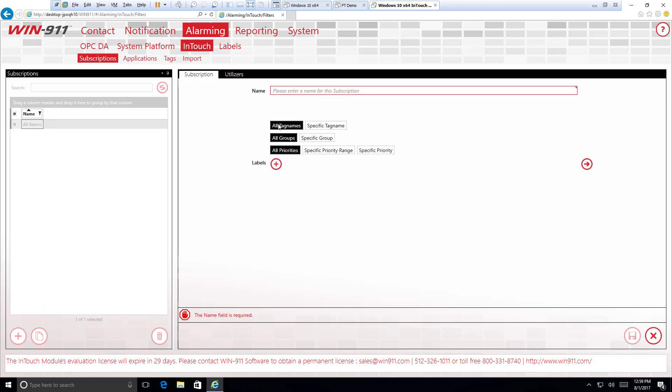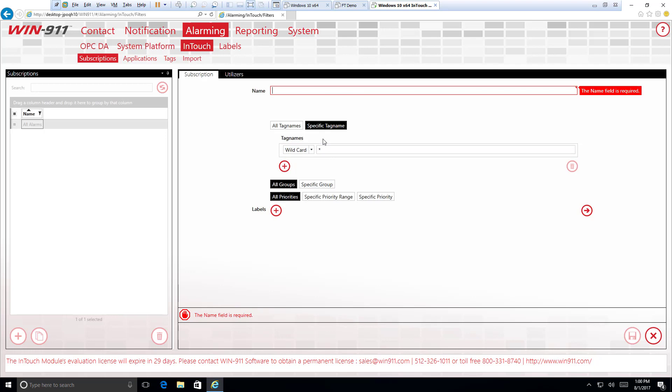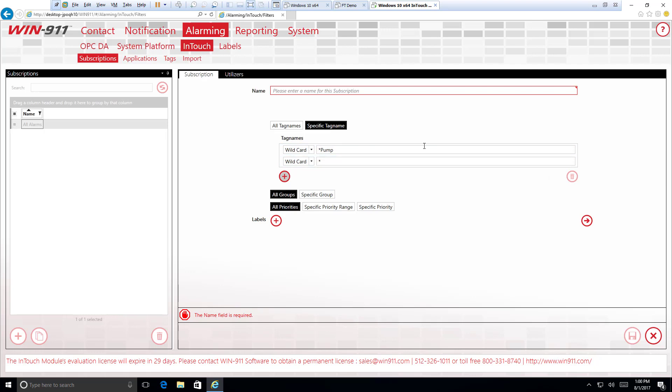But let's actually start by creating our own here. And you'll see in general we have three different aspects that Win911 allows you to alarm upon: tag names, groups, and priorities. So first we'll take a look at tag names. And we'll see a dropdown that is very similar to the rest of the subscriptions where we have a wildcard, regular expression, contains and does not contain. First we'll start off with a wildcard. These are pretty simple. They allow us to catch any alarm or tag that has a certain word in it. So let's say our word will be pump. This will allow us to catch any alarm that has the keyword pump in it with any other strings surrounding it.